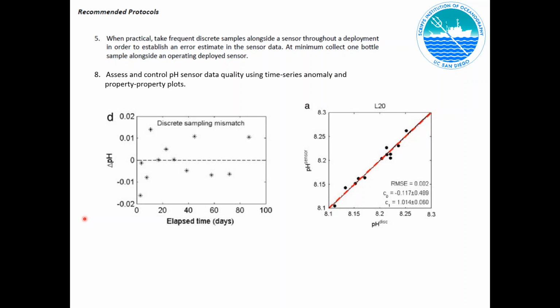In my opinion, correcting bad data, it's very hard to come up with good data. It's normally better to throw out the bad data altogether. But maybe that's a discussion topic. It is, like I say, a matter of opinion, I think. Once you've quality controlled it in an anomaly plot sense, you can sometimes apply a correction to the calibration in post-processing using some type of a property plot. What we're looking at on the right is a sensor versus bottle measurement property plot, and doing a simple regression through it. You could, for example, use a slope and intercept to correct the sensor data to come into agreement with the bottle data.